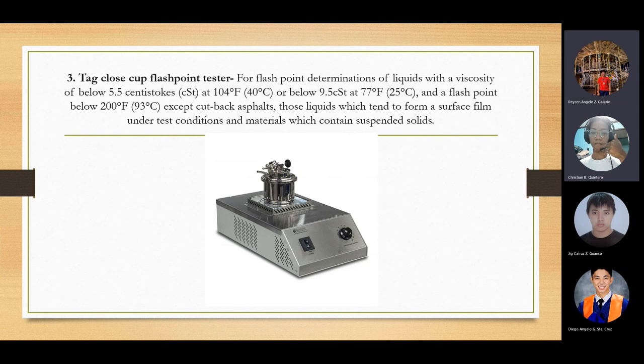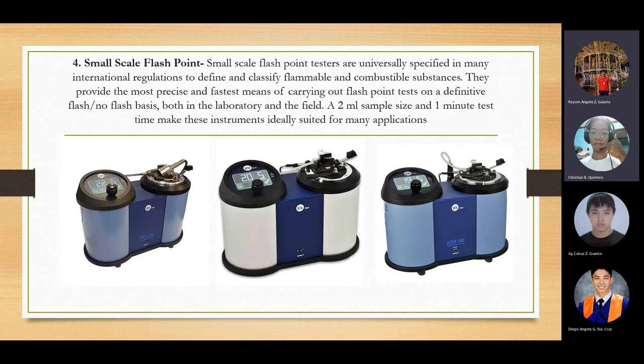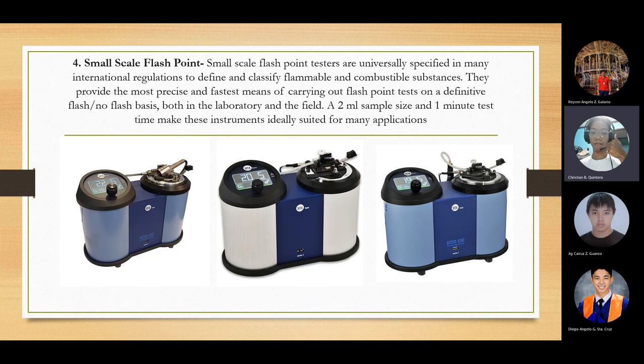A closed flashpoint tester for flashpoint determination of liquids with viscosity below 5.5 centistokes. This measures flashpoint, the lowest temperature at which vapors of a sample ignite upon application of an ignition source. Small-scale flashpoint testers are universally specified in many international regulations to define and classify flammable and combustible substances. They provide the most precise and fast means of carrying out flashpoint tests on a definite flash, no flash basis, both in laboratory and field. A 2ml sample size and one-minute test make these instruments ideally suited for many applications, such as rapid test of flammability.